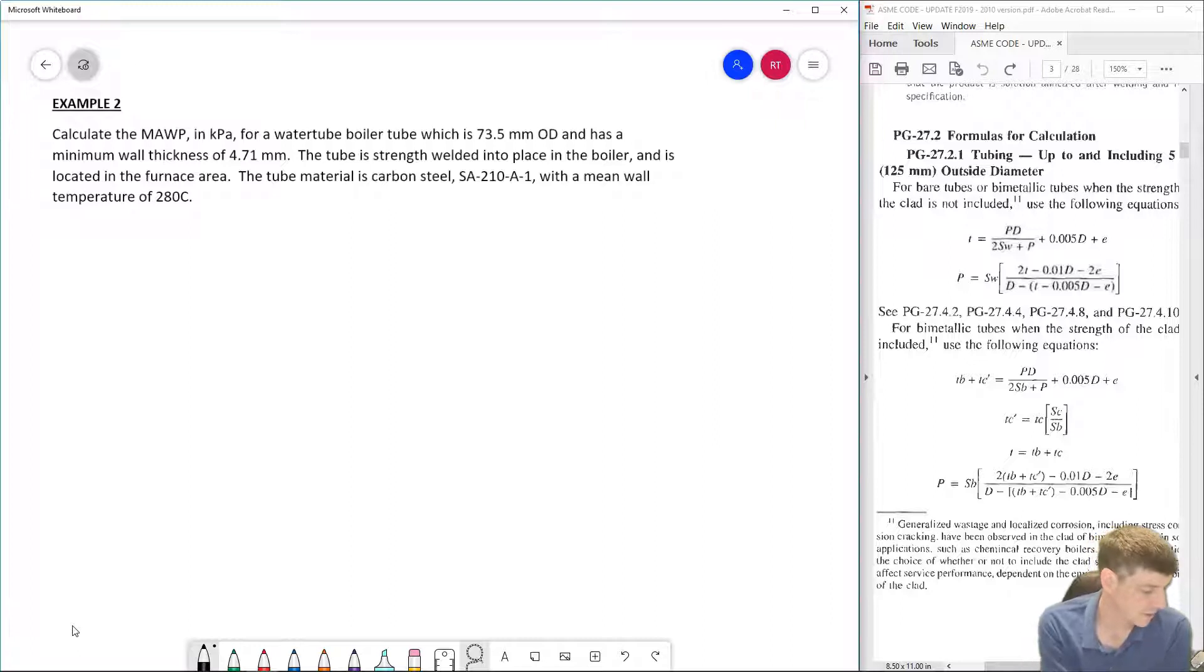Okay, same process that we're going to go through before. First thing we want to do is identify that this is a tube, and the tube is within the limits for tubing - 125 millimeters outside diameter maximum. And it appears that it is, so we are able to use our formulas out of our code for tubing. Because we are looking for our MAWP, we are going to use the pressure version of our formula.